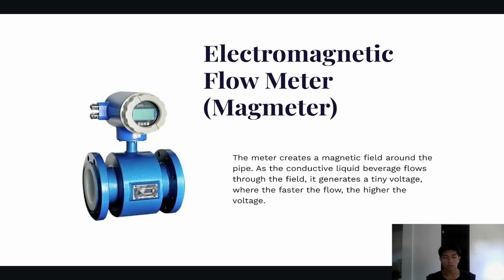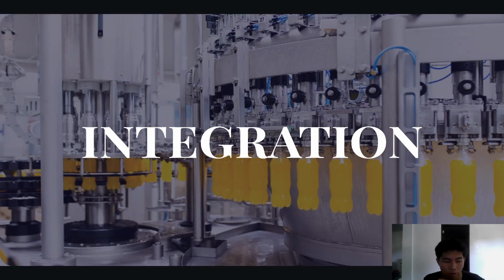It flows through the magmeter, or through its pipe, to calculate the amount of liquid beverage that has passed through. It can be calculated since the pipe diameter is exact, given or already known to the person that manages the system. Therefore, what only needs to be measured is the amount of liquid beverage that is passing through, which is measured by the flow meter, or the magmeter.